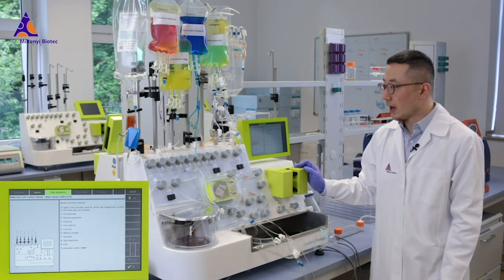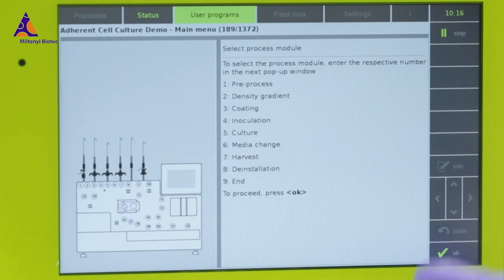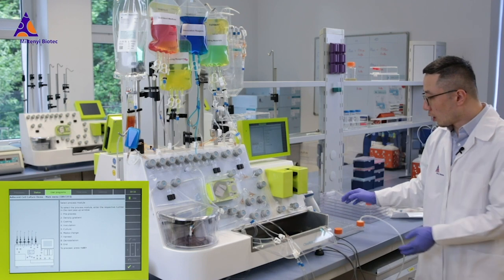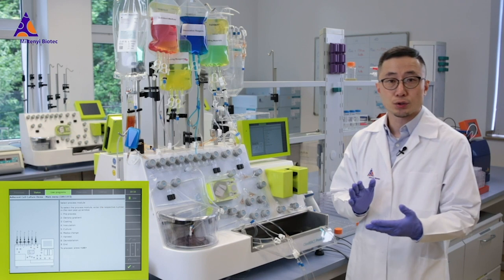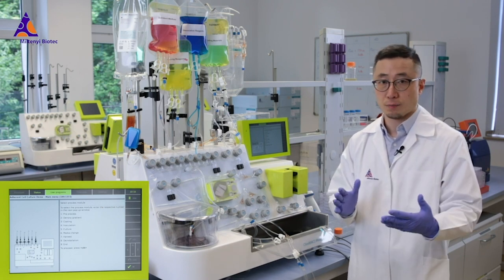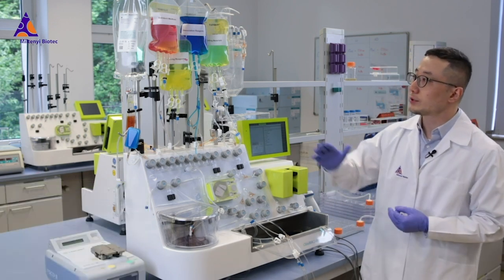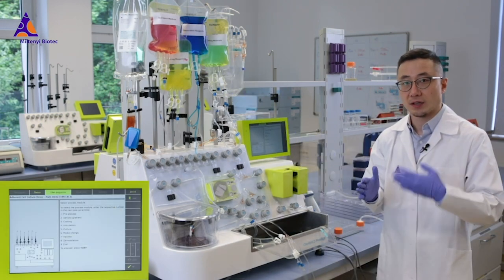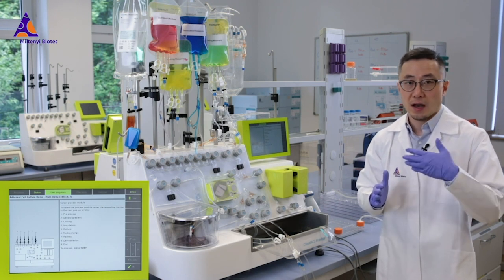During the cultivation process, if we want to do a medium change, we use the medium change module — module number 6. Users can do the medium change in the Prodigy Chamber in the CCU, or in the external culture vessels. Users can also choose complete medium change or partial medium change according to their SOPs, and can use CliniMACS buffer or standard medium to rinse the cell cultures and remove debris or dead cells.